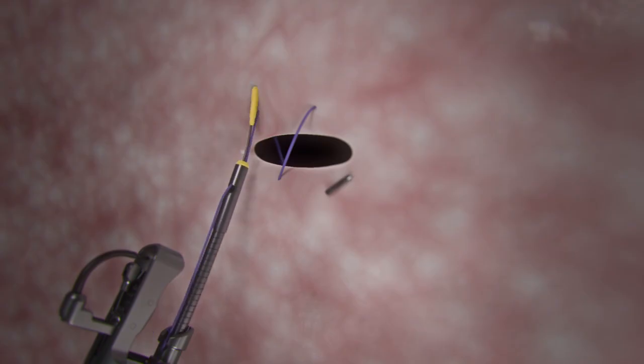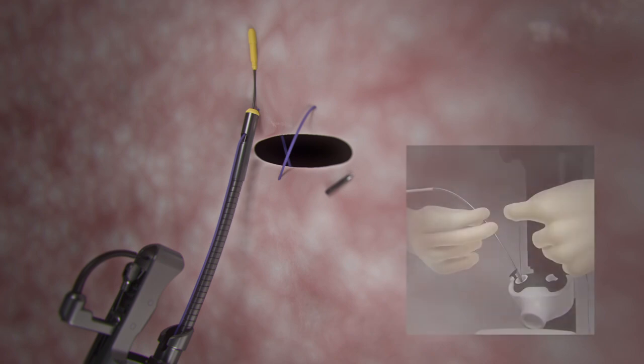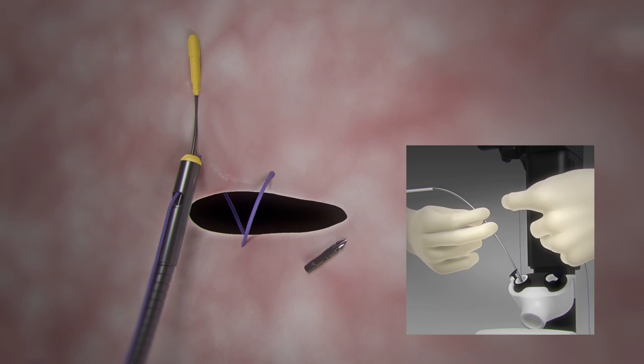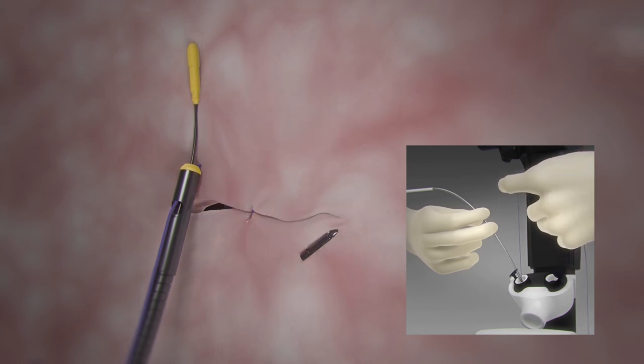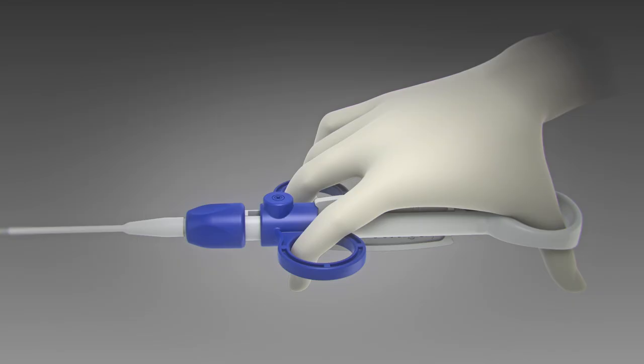Advance the cinch catheter until it extends approximately 3 centimeters past the overstitch end cap, targeting the placement of the first bite. While holding the cinch catheter in place, apply tension to the suture with small increasing increments of force. Care should be taken not to pull the suture too tight, resulting in breakage.